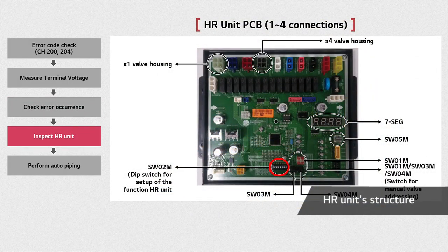Inspect the HR unit. The structure of the HR unit's PCB is shown. First, check the DIP switch in the PCB. As shown in the picture, the number of indoor units can be set by using the HR unit's SW02M DIP switch, specifically switch number 2 and 3.